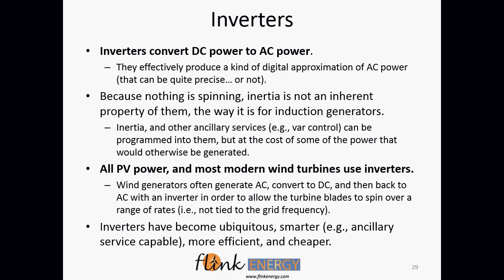You turn down the inverter. So let's say the solar project can produce, I don't know, 10 kilowatts at a particular moment. But instead of the inverter letting all 10 kilowatts go by, it only lets, say, 9.9 kilowatts go by. And then if it senses some problem on the grid, it can blast through that last little bit that looks like inertia. They can be programmed to do VAR control.